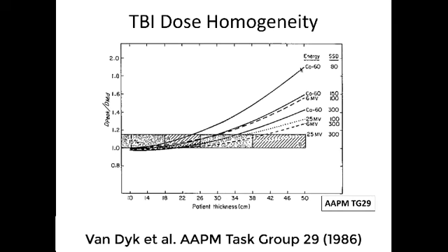It's for cobalt beam, and you'll see that as the patient gets thicker, it becomes less homogeneous. That's what you saw in those previous curves. Remember the 6x versus the 18x. The lower energy beam has a big inhomogeneity. Now as you go to higher energy, that effect falls off. It becomes more homogeneous here at 6 MV. And then here's at 25 MV. Okay, so the same effects that we were seeing in the plots, now just plotted quantitatively.